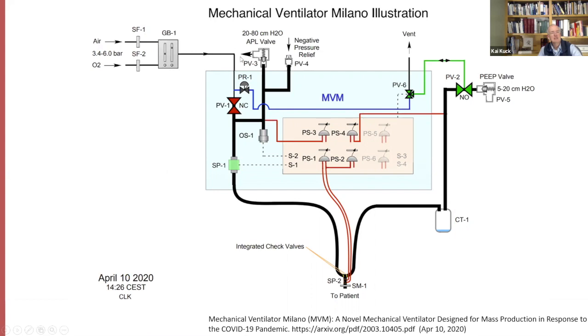And then this one is a pressure relief valve in case something goes wrong. You make sure that you don't blow up the lungs, you don't cause any barotrauma. And here's a pressure relief valve just in case this valve gets stuck in a closed position. Say the patient wants to take a breath, but right now it's closed because the machine doesn't think it should give a breath. The patient can actually take a breath and get it from here.